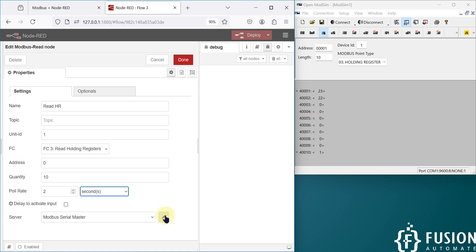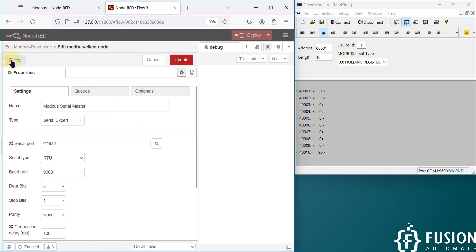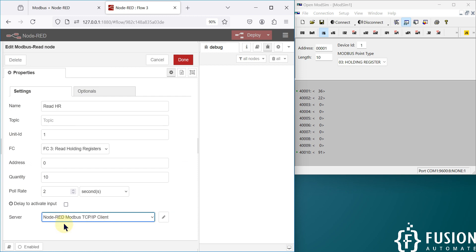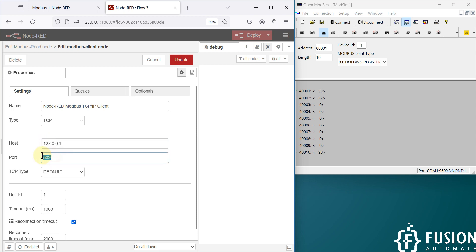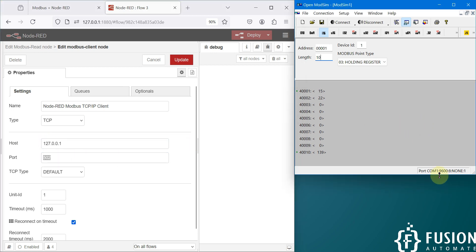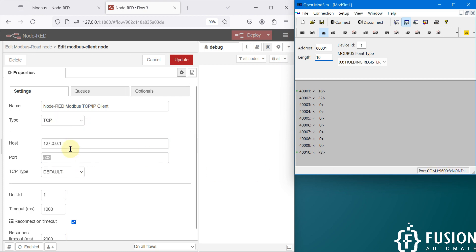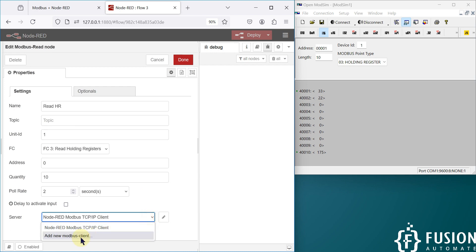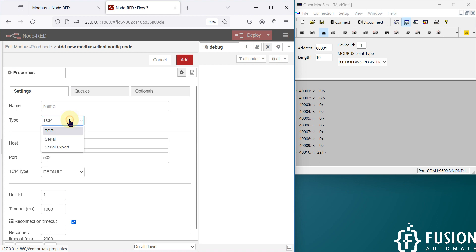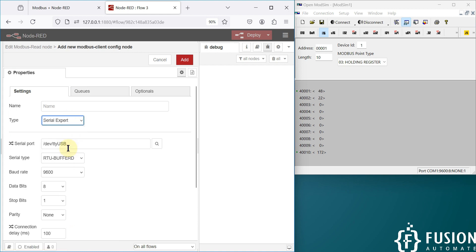Let me delete the old node first. Previously we created a Node-RED Modbus TCP/IP client to read data from a Modbus TCP device, but this is a Modbus serial device. The TCP/IP client uses an IP address and port number, but to connect with a Modbus serial device we need COM port, baud rate, data bits, parity, and stop bit — that configuration is not available when you select TCP. So you have to add a new Modbus client, click the pencil icon, and instead of TCP select Serial Expert.